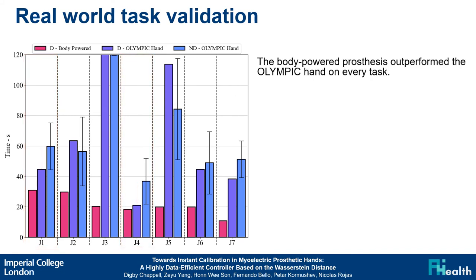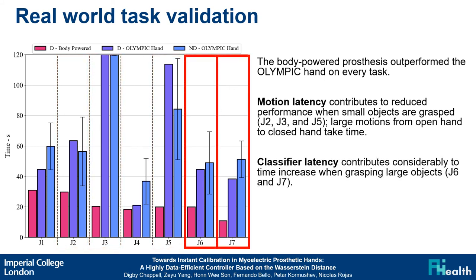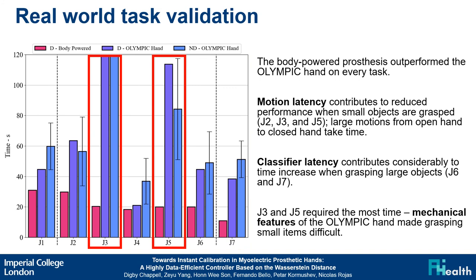In all tasks, the disabled participant using their body-powered prosthesis outperformed all participants using the Olympic hand. In tasks involving small objects such as J2, J3, and J5, the distance that each finger must travel to close the hand is quite large, and therefore motion latency has an impact on performance. In tasks J6 and J7, the objects grasped are large, so the distance each finger must travel is relatively small; in these tasks, classifier latency contributes significantly to the time increase. Finally, the mechanical design of the fingers of the Olympic hand means it may require several attempts before a precision grasp is achieved, which compounds the effects of motion latency and classifier latency, accounting for much of the time difference observed for J3 and J5.